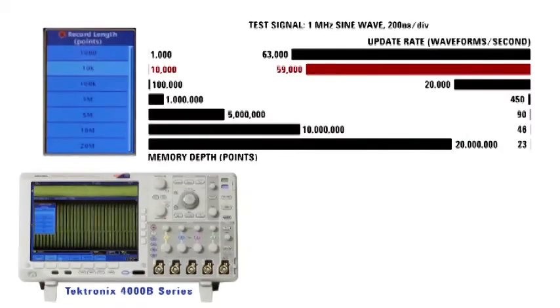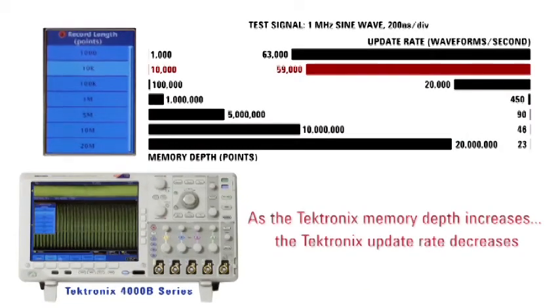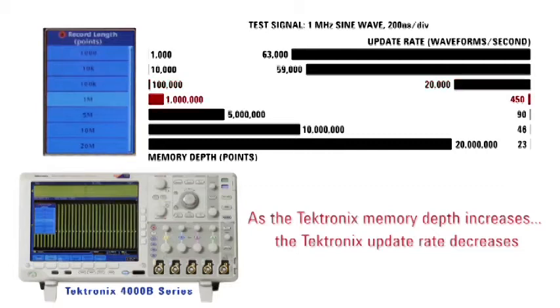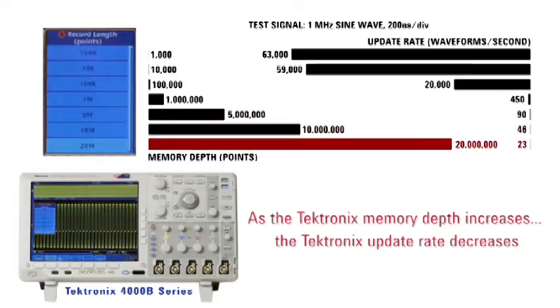Tektronix defaults their memory depth to just 10,000 points, and it must be adjusted manually by the user because of the trade-off between memory depth and update rate.